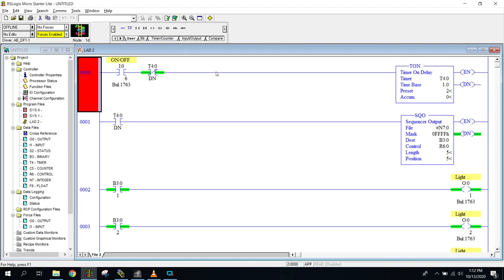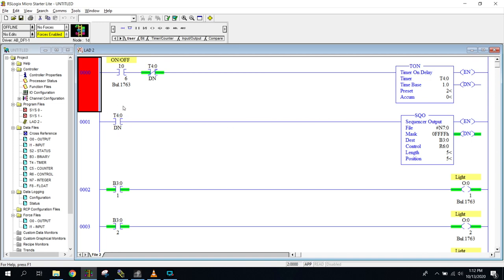So remember how free running timer works: we're going to have a path of true and every time the timer is done it's going to break the path of true causing the timer to reset which again makes a path of true. So every two seconds is what I have my preset to. It's going to reset this timer. So meaning every two seconds our done bit down on the second rung here will go on and then off causing our sequencer to move one step further along. So I'm going to go ahead and download and we're going to see this in action.